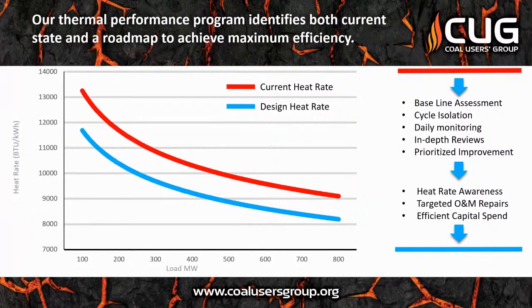In setting up the program, we conduct a baseline assessment to establish where the unit is operating. Then we perform daily monitoring, cycle isolation monitoring, and in-depth reviews to point to issues that could impact heat rate. This information is used along with the plants to target O&M repairs and capital spend to help sustain heat rate improvements.